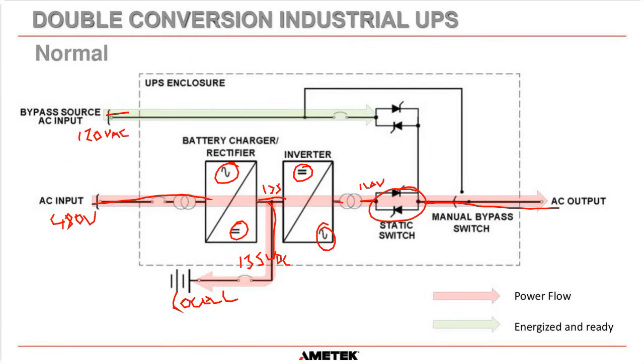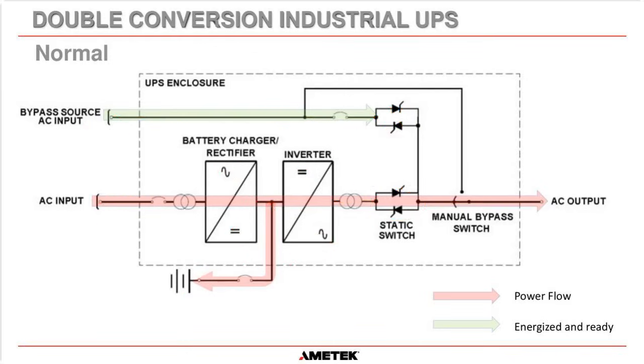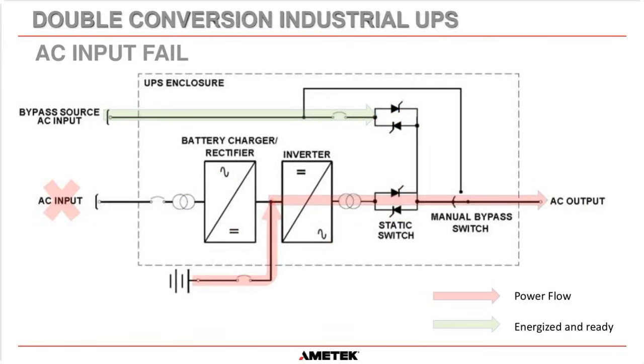It's ready to go. It's energized. It's 120 volts coming in, and it goes to this static switch, but this static switch is off, and it's just waiting to be told to turn on if there's an issue with this inverter here. So no power flows from the bypass into the load circuits in normal operation. Very similar to the commercial UPS.